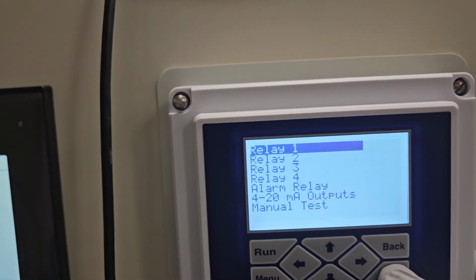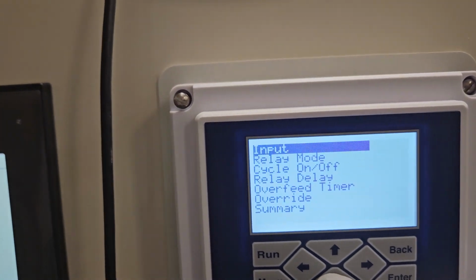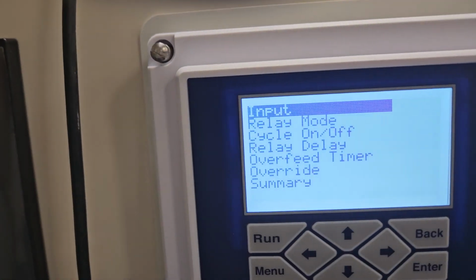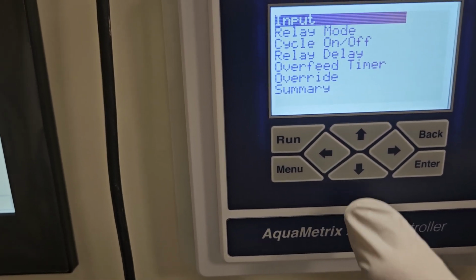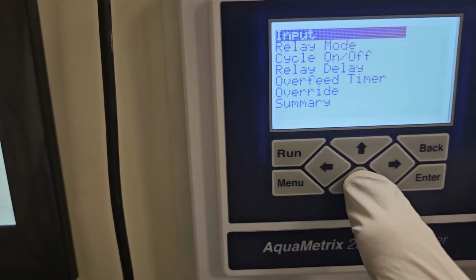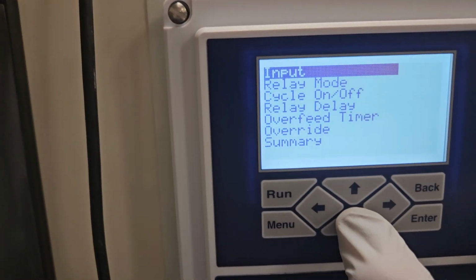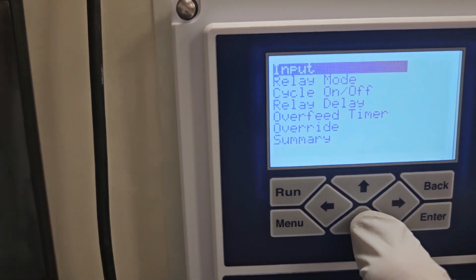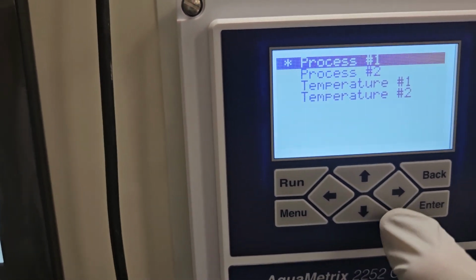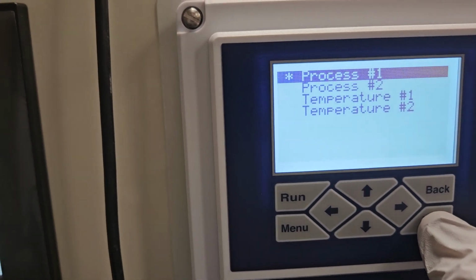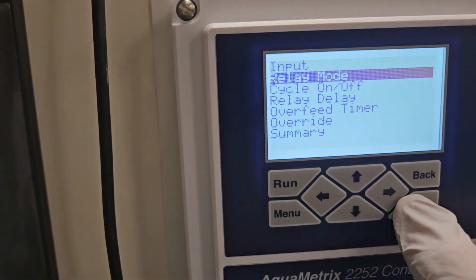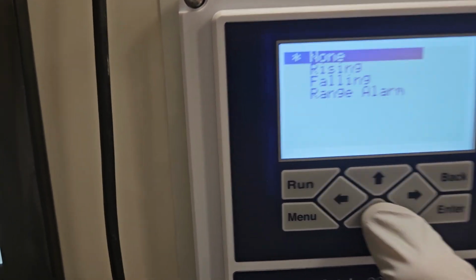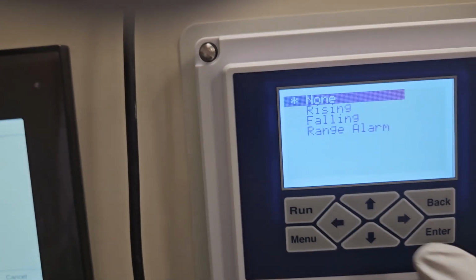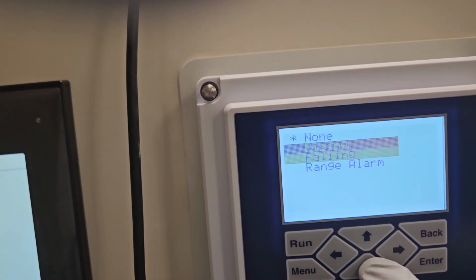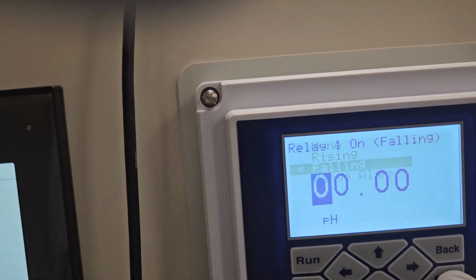Relay 1 is going to be set up for, hang on. So when we set up our relays, the first relay, either denoted with A or on this particular relay, it's 1. So input 1, process 1, the relay mode is going to be falling for addition of caustic. So caustic control would be falling.